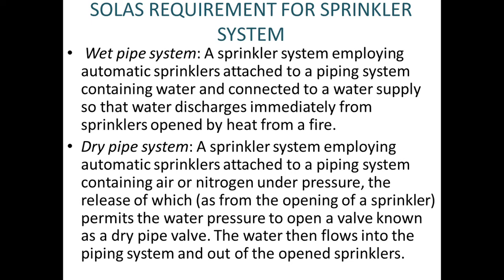When we talk about the wet pipe system, it is a sprinkler system employing automatic sprinklers attached to a piping system containing water and connected to the water supply, so that water discharges immediately, because up to the head of the bulb above the diaphragm, in the diagram that I showed, the water is available till there. As soon as the bulb breaks, the water immediately and continuously starts flowing.